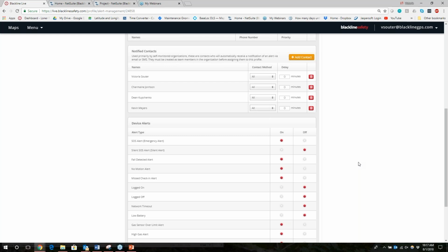However, if Charmaine, Dean, and Kevin said, you know what, Victoria's the manager, so I want her to respond to the alert. I only want to get it, and Dean and Kevin only want to receive it, if Victoria can't attend to it. Then I would suggest maybe putting everyone on a minute delay. So we could say, okay, Charmaine, we'll put you on a 2-minute, we'll put Dean on a 4-minute, and we'll put Kevin, who's like the safety director, at 6. So what that's done is it's kind of layered in: if Victoria does not respond to that alert within 2 minutes, it's then going to be sent to Charmaine, and so on. So you can structure it in 2 different ways for self-monitoring.